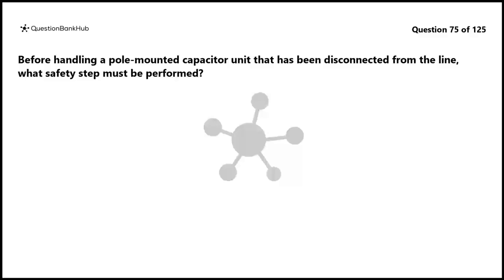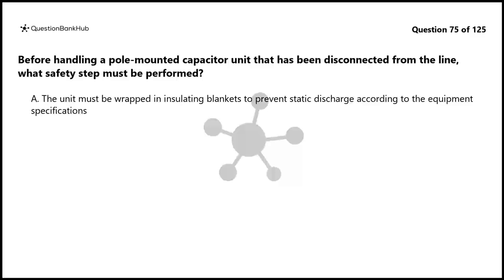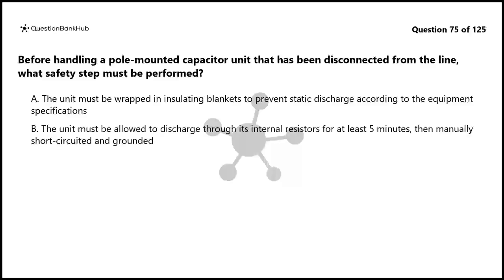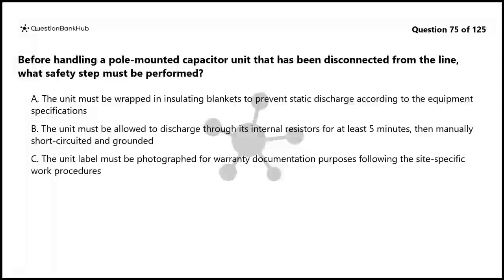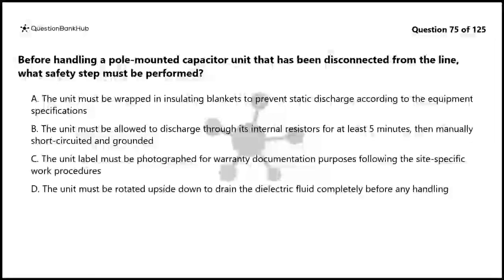Question 75. Before handling a pole-mounted capacitor unit that has been disconnected from the line, what safety step must be performed? A. The unit must be wrapped in insulating blankets to prevent static discharge according to the equipment specifications. B. The unit must be allowed to discharge through its internal resistors for at least 5 minutes, then manually short-circuited and grounded. C. The unit label must be photographed for warranty documentation purposes following the site-specific work procedures. D. The unit must be rotated upside down to drain the dielectric fluid completely before any handling.